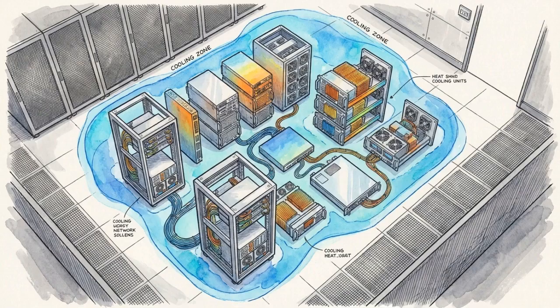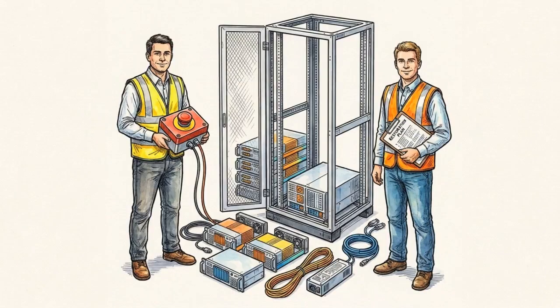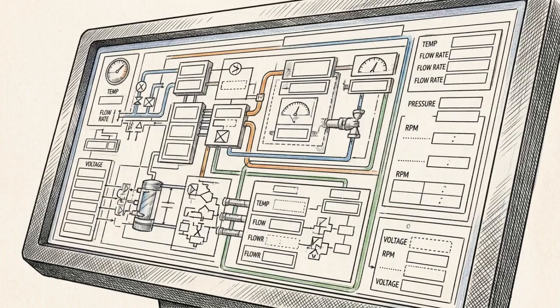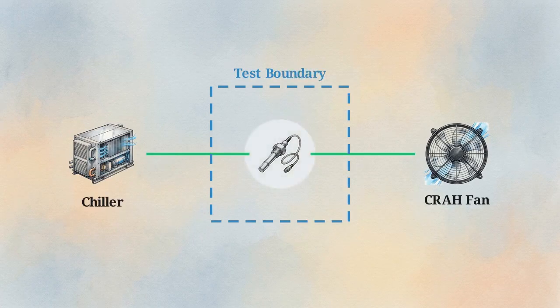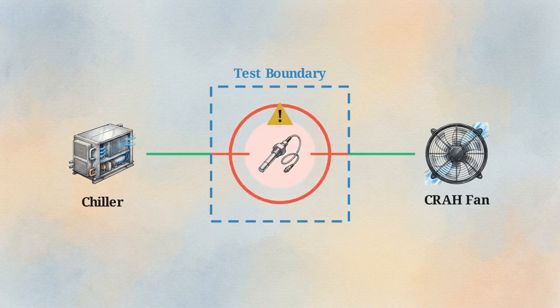Every validation procedure relies on a strict testing boundary. You need an approved initial state and exactly one controlled disturbance. Furthermore, no script begins without a named stop work authority and a clearly defined restoration owner physically present on site. You simply cannot test an undefined system. By strictly enforcing these boundaries, we ensure that a single localized oversight, like one miscalibrated sensor, cannot escalate into a catastrophic facility-wide cascade.